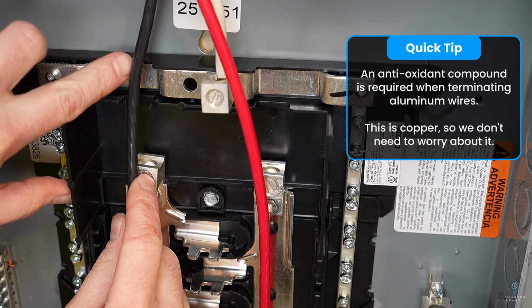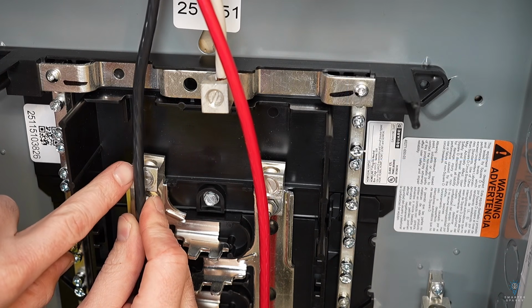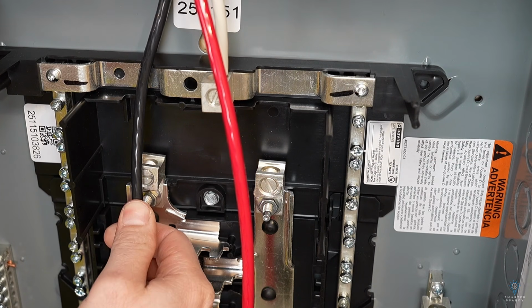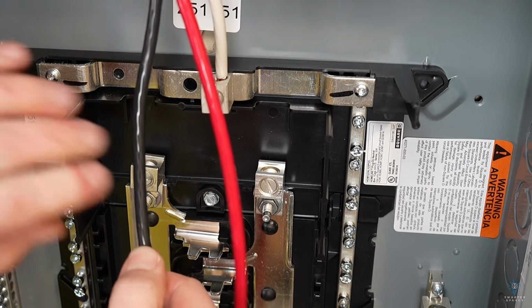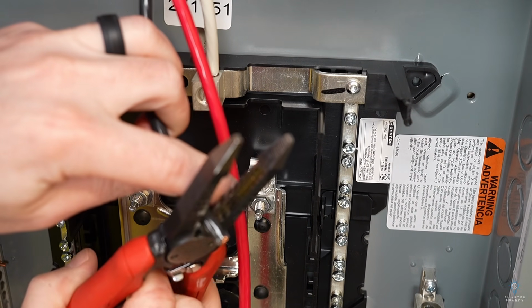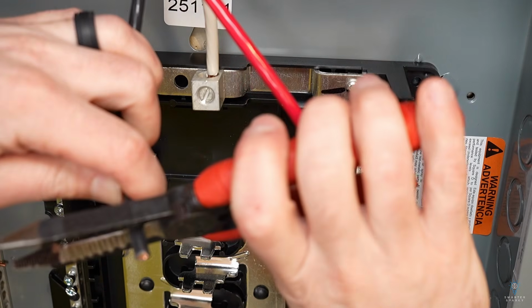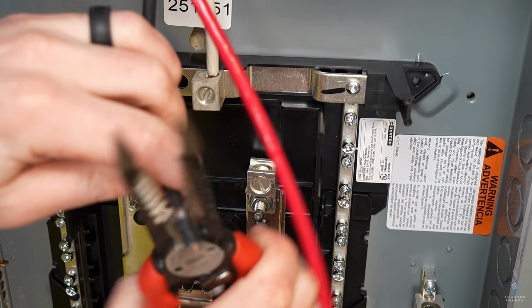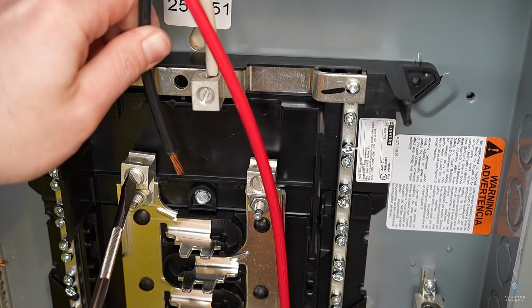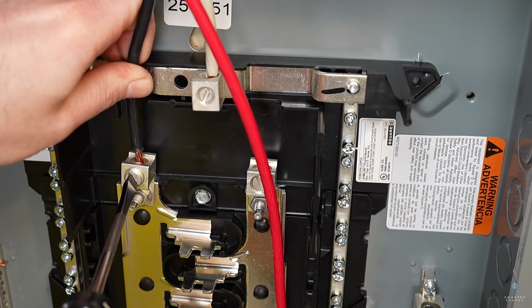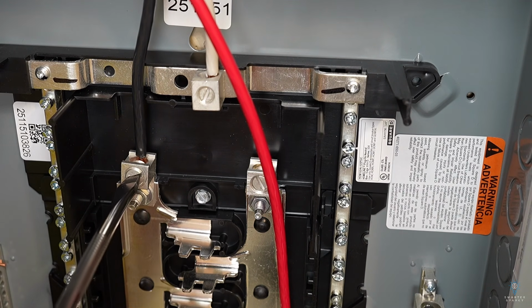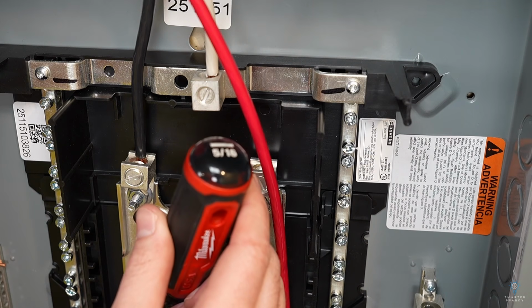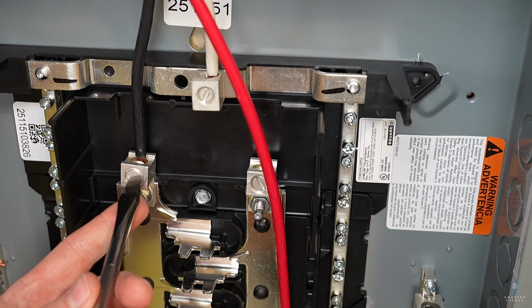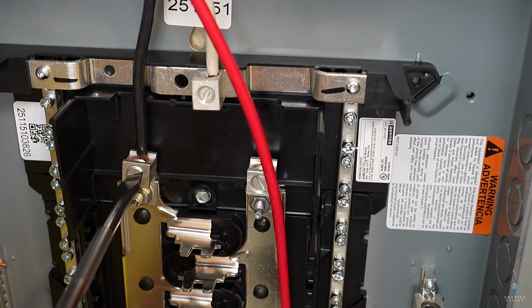And then the black wire, we can give it a slight little bend right here so it lines right up with the lug. I'll mark the end of where I want it cut with my thumb, cut it to length, and then again, we can just strip it out with the wire cutting portion on the wire strippers. And then we can install it under its appropriate lug. This is where having multiple size screwdrivers comes in handy. This is a 5/16 screwdriver, and it fits these particular lugs just a little bit nicer.